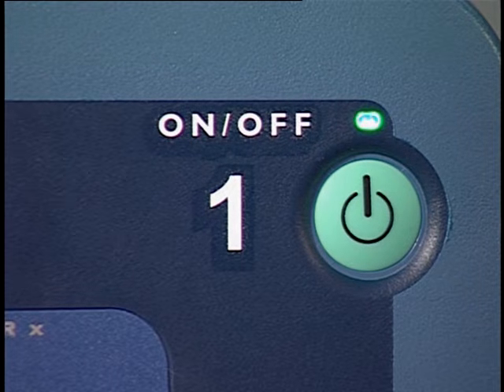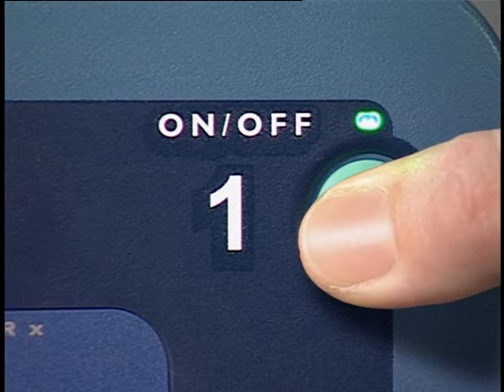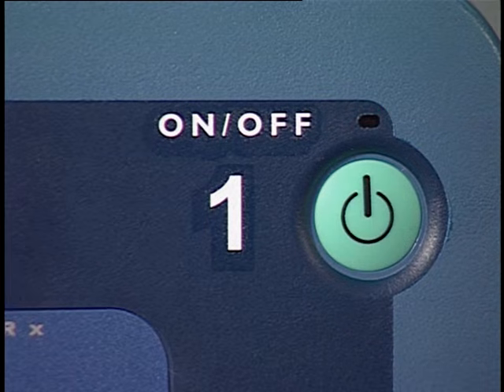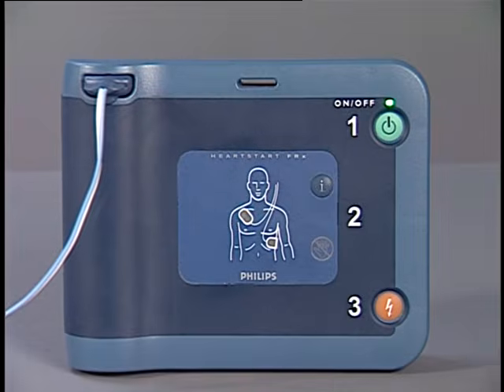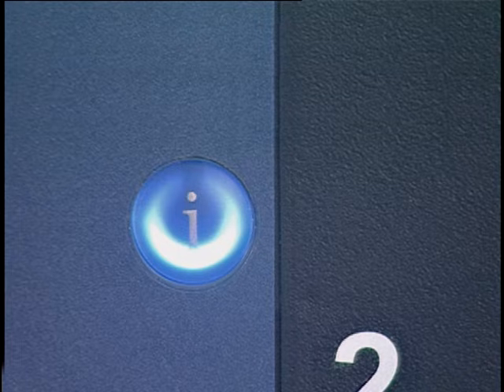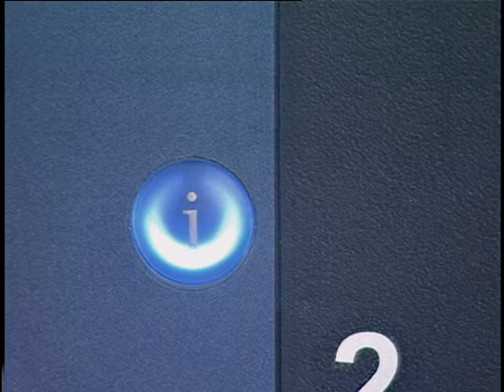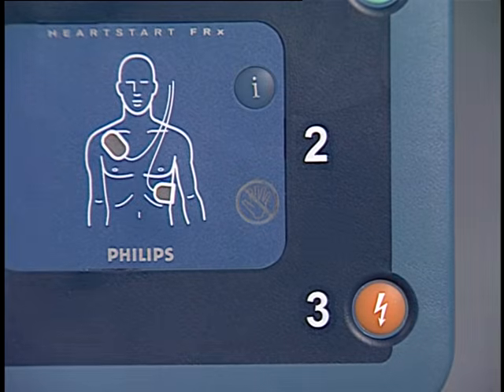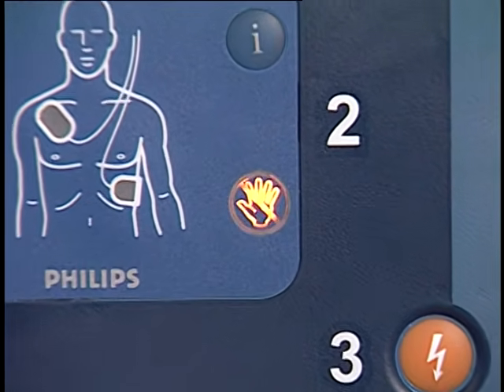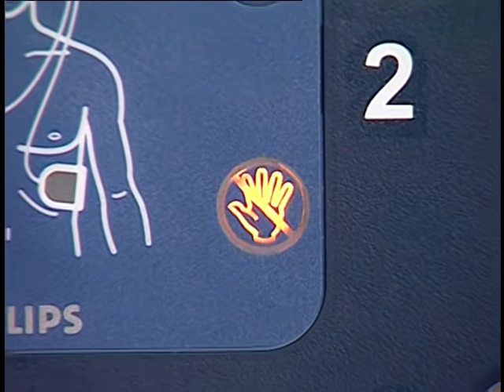The on-off button is also used to turn off the FRx at any time by holding it down for 1 second. Near the center of the panel is a blue button with an i on it. This is the information button, or I button. If you press the I button while it is flashing, the FRx gives you information, such as optional CPR coaching, device status, or troubleshooting help. Below the I button is the caution light. It has a symbol of a hand with a line across it to represent "Do not touch the patient."